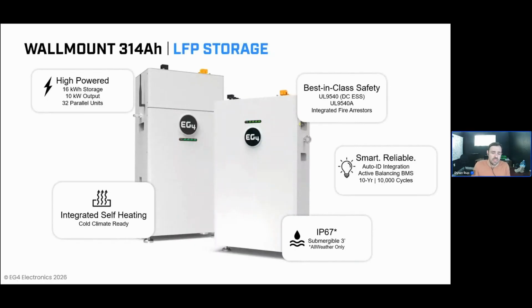system. Beyond that, this unit has been subjected to large-scale fire safety testing and shown to not propagate fire even from the cell-to-cell level, meaning it's a very safe solution. And more impressive than that, and really going the extra mile, in order to run that fire safety test, you actually have to start a fire within the battery to see how the battery performs. What this means is the integrated fire arresters that we include in every single unit had to be pulled out in order to perform the test reliably and get a result. So realistically, even without the integrated fire arresters that do come standard, this unit has shown to be incredibly safe in the event of any type of thermal runaway.